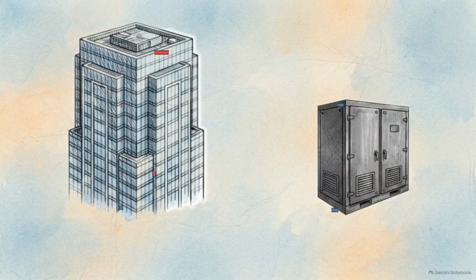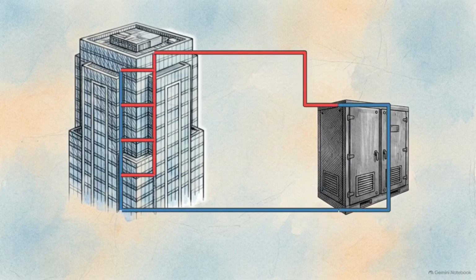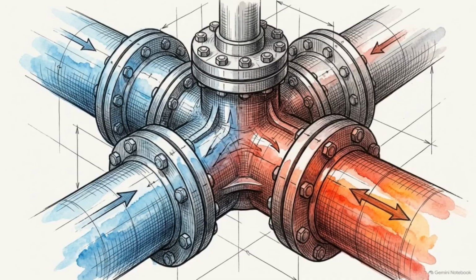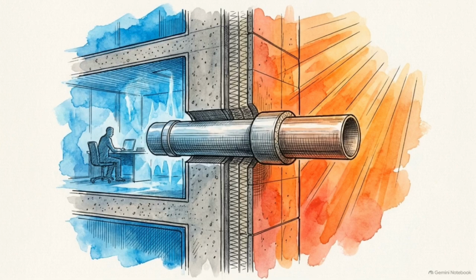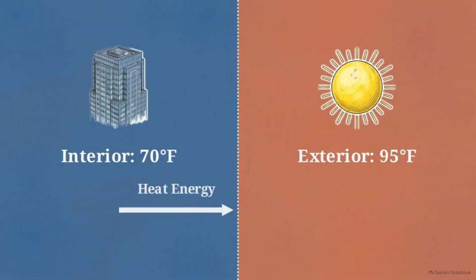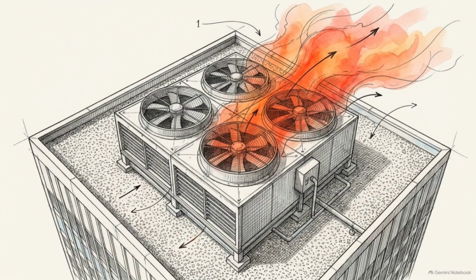The chiller operates as a high-capacity heat extractor. It pulls thermal energy out of the building's internal water loop, lowering the water's temperature so it can be sent back through the structure to absorb more heat. This makes the chiller a thermal transport mechanism. It is designed to bridge the gap between the heat generated inside the building and the environment outside. This presents a strict thermodynamic challenge. Moving heat energy out of a building requires forcing it against a natural temperature gradient, so it can be rejected into the warmer external environment.